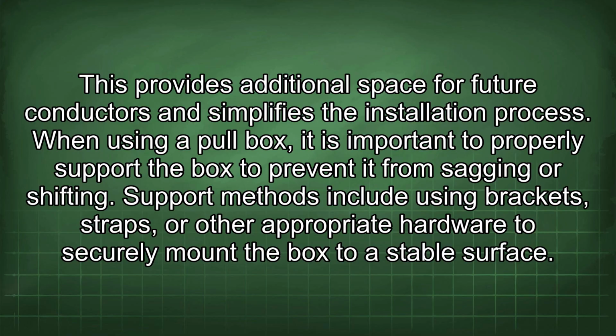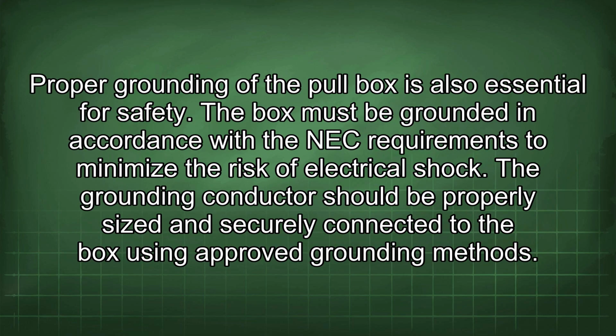When using a pull box, it is important to properly support the box to prevent it from sagging or shifting. Support methods include using brackets, straps, or other appropriate hardware to securely mount the box to a stable surface. Proper grounding of the pull box is also essential for safety. The box must be grounded in accordance with the NEC requirements to minimize the risk of electrical shock. The grounding conductor should be properly sized and securely connected to the box using approved grounding methods.